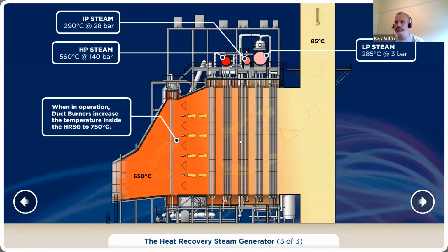Now, as it goes through the boiler, the temperature going up the stack is 80 to 90 degrees. You don't want to drop the temperature too low because you still need a bit of energy to get the gases up and out. If the temperature is a bit too low here, you might lose a bit of buoyancy and you wouldn't make it out the top of the stack.